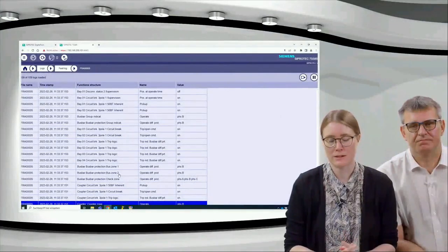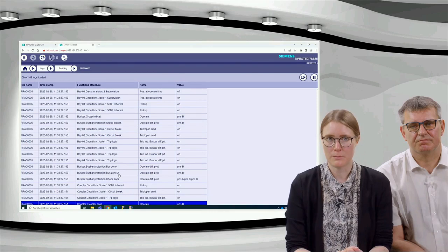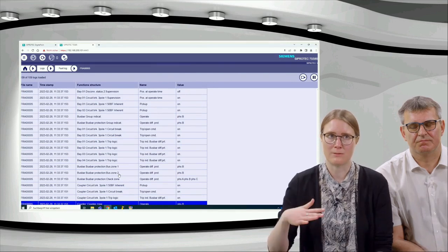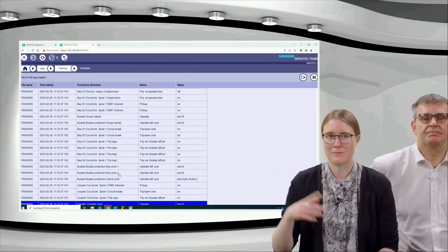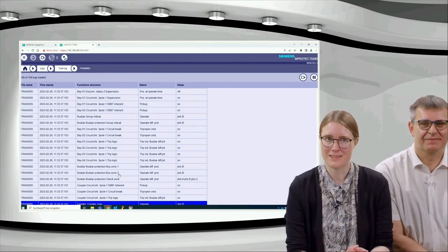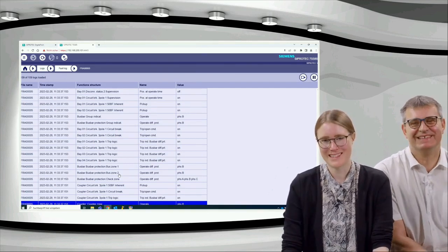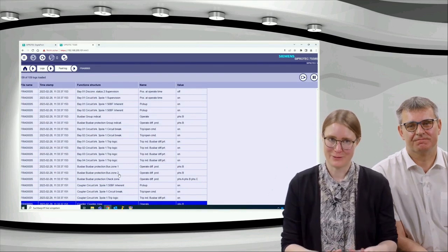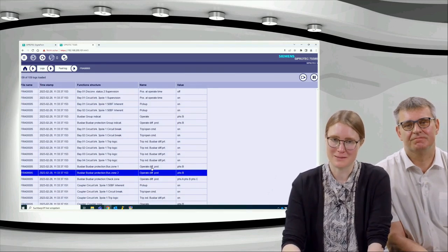This means as soon as we have a differential current above the threshold and for 3 phases, then we will immediately trip both bus zones in overlapping mode. And the second threshold was set to 5 amps, and this was the threshold for the 1-pole faults. That means as soon as we exceed these 5 amps, then we will also get to overlapping mode for 1-pole faults. But in between, so for currents smaller than 5 amps, and with a 1-pole fault, of course, there will be a selective tripping with the end fault protection involved. But the first test scenario was the 3-pole fault. So this is why we see here this operate for both bus zones.